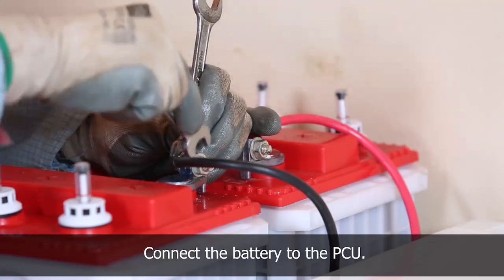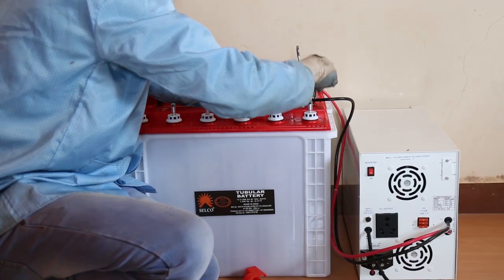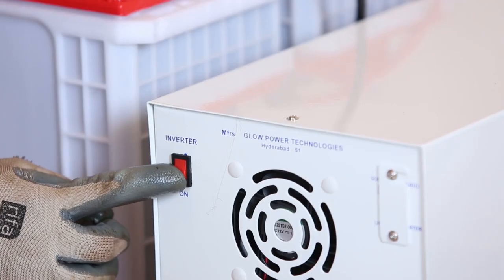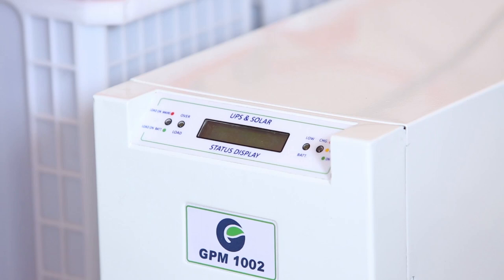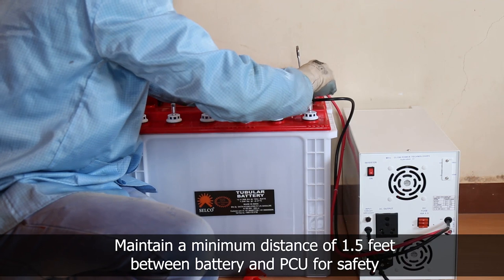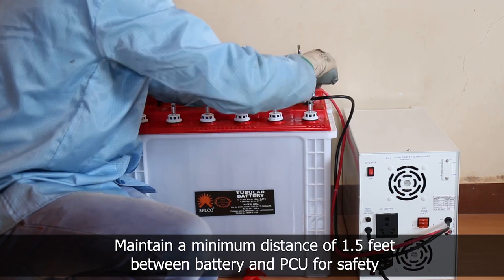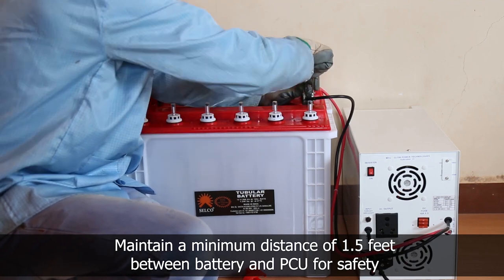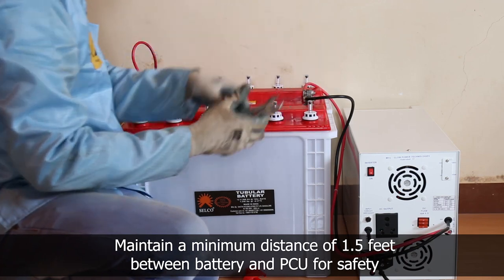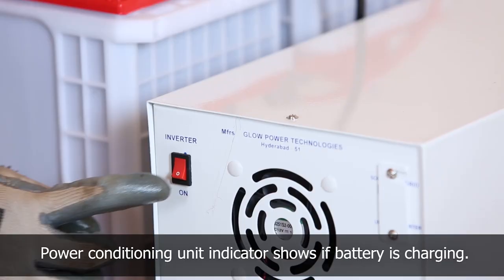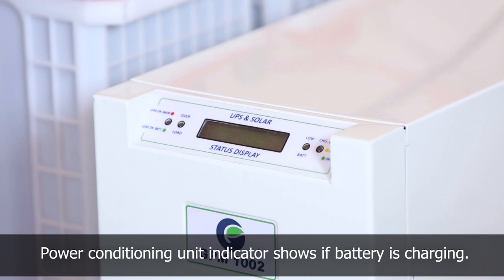Before connecting the cable to the power conditioning unit, ensure that the battery and the miniature circuit breaker are switched off. Make sure to maintain a minimum distance of 1.5 feet between the battery and the power conditioning unit for safety reasons. Switch on the power conditioning unit and the miniature circuit breaker and check the indicator for battery charging.